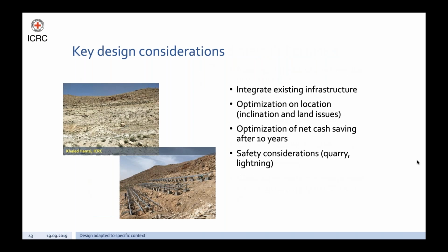When we talk now about the solar systems, I present you quickly the key design considerations. One was to integrate the existing infrastructure. The solar system had to be designed to accommodate that, for example, to run the existing AC pumps. The same pump also runs regularly on the medium voltage power line or on a backup generator. The idea was to solarize them and install inverters. This had implications on sizing and the choice of electrical equipment.